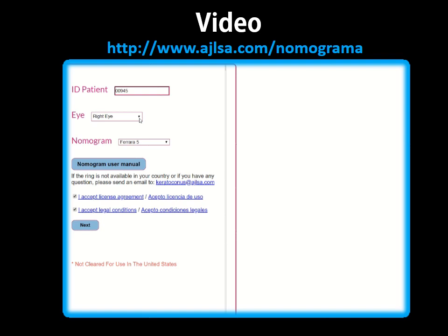After that, I will print the form. And as you can see here, it gives me everything: the incision size, the incision length, the incision depth, the segment. For example, here the segment arc 220 and the thickness should be 150, and it gives me the shape of the ring where it can be inserted in the cornea, and this is the incision size and this is the incision depth, of course, with the femto tool place.